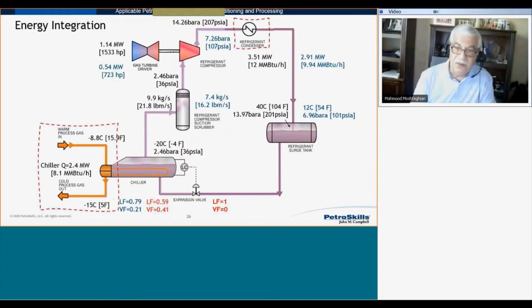Again, just a comparison. If the condensing temperature was 104 degrees Fahrenheit, the mass flow rate was 21.8 pound mass per second, but using the cool process, my mass flow rate went down to 16.2 pound mass per second, and the power requirement also went down from 1,533 to only 723 horsepower. I'm going to skip the rest of it because I have a summary table to save some time.